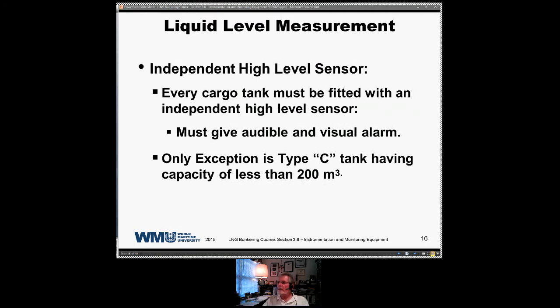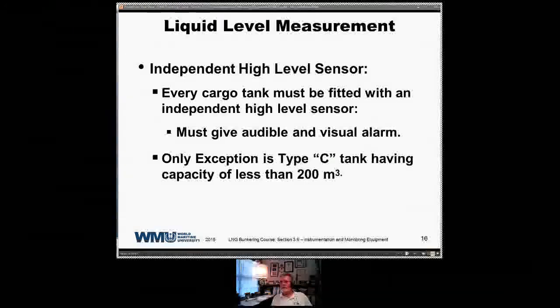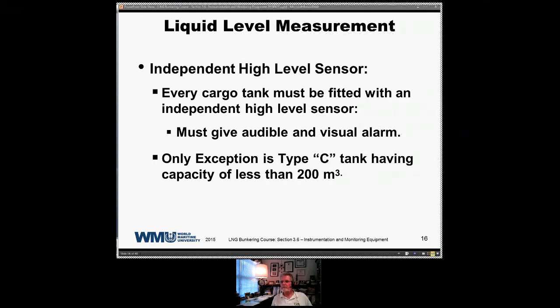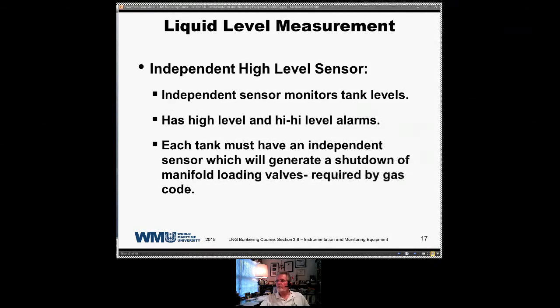Each tank is going to be fitted with an independent high-level sensor. Every cargo tank must be fitted, and it must give an audible and visual alarm. The only tank that is excluded from this is a Type C tank. Those are the high pressure tanks, 150 psig, with a capacity of less than 200 cubic meters. So this includes your tanker trucks, which are Type C tanks. They do not have to have an independent high level. The independent sensor monitors the tank level, and it has a high level and high-high level alarm.